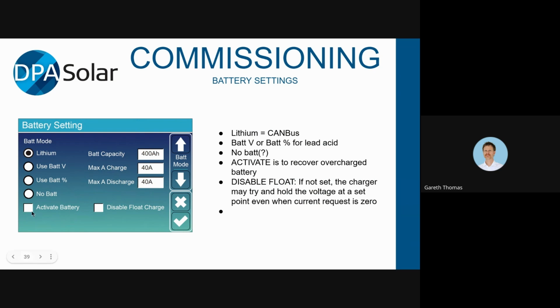Activate battery is something you can turn on to recover an over discharged battery. And disable float, it's probably a good idea to have that on so the charger doesn't try and hold the voltage at the top set point, even when the BMS is requesting 0 current. If you're using something like a Discover battery, it wouldn't be as much of a problem because they actually change the voltage in their request from the BMS through to the inverter. So once they go through their absorption cycle, they'll then request a lower voltage anyway. But other BMSs might not be as dynamic as that, and they might still broadcast that top voltage even at the end of the charge cycle and just request a 0 current. So it's a good idea to have disable float charge on for lithium batteries.